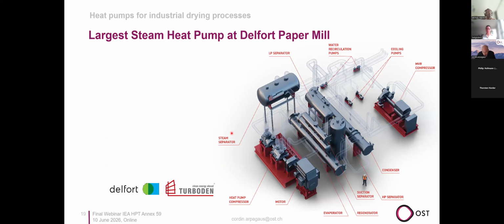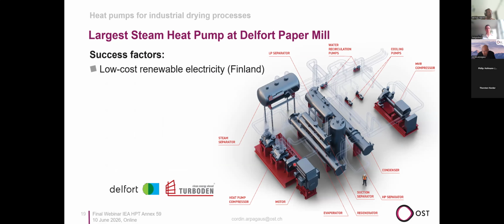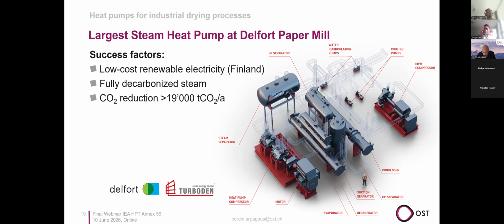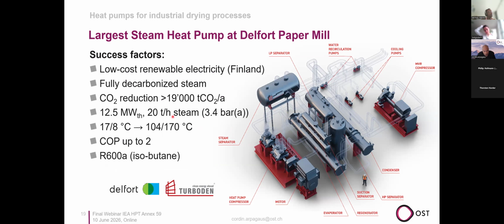Then another example in the paper industry, this is the largest steam generating heat pump, I think at the moment, from Turboden. So this is in Finland, where they have quite a low electricity price. So the business case was favorable. And this reduces the fossil fuel steam generation. 19,000 tons of CO2 can be reduced, and it's a 12.5 megawatt installation, 20 tons per hour steam. Here you see the temperature conditions. It's quite a high lift, and the COP is up to 2. What is also interesting is isobutane as a refrigerant, a hydrocarbon fluid.